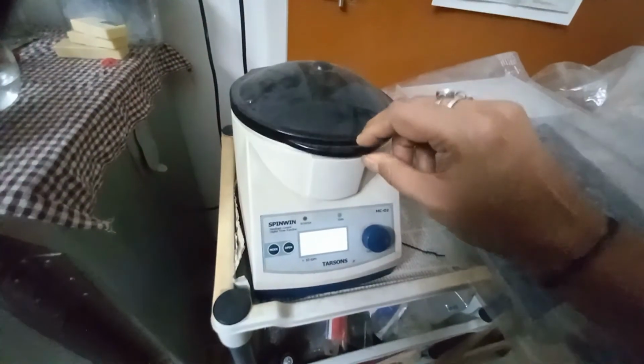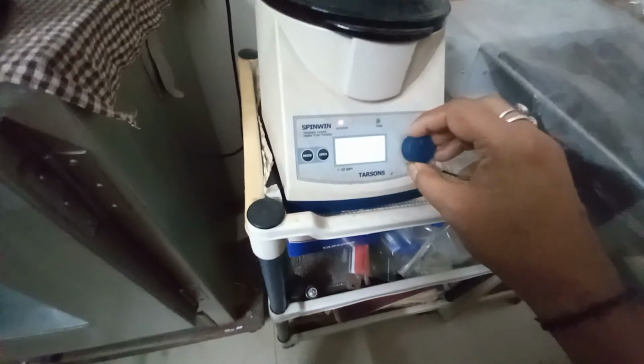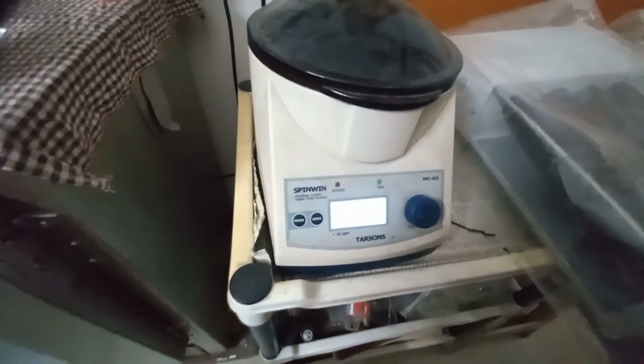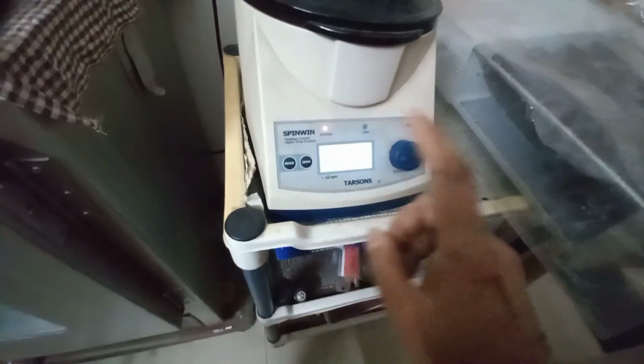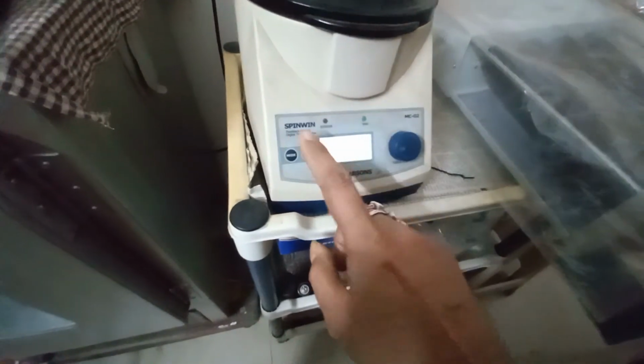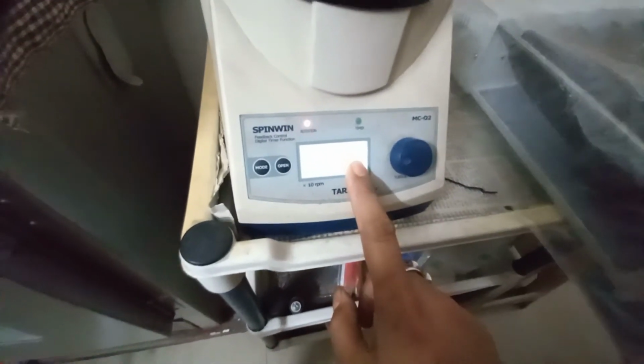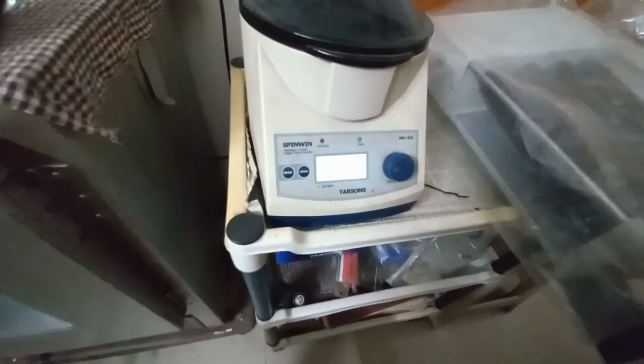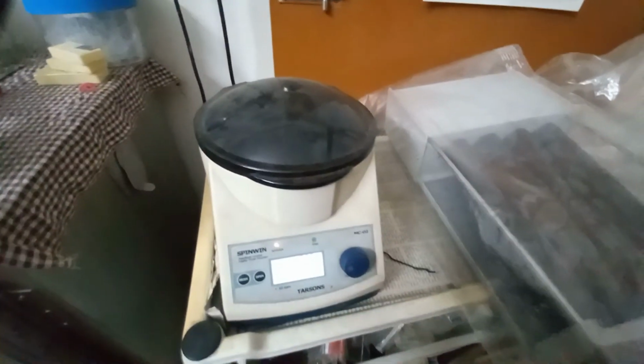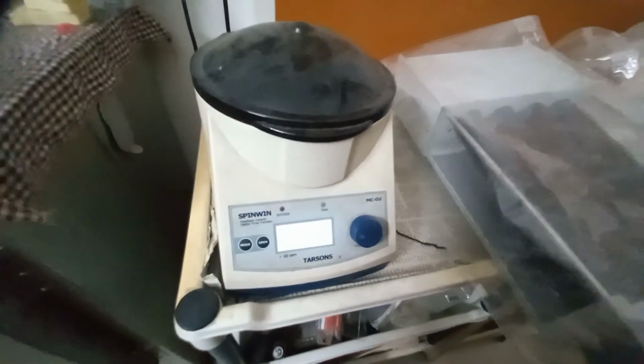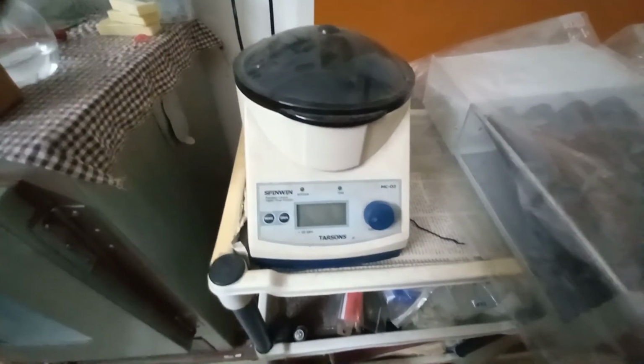Then you close the centrifuge and you start controlling. First you have to control the speed, then you have to change the mode and set the timer. Then again you bring it to the first display mode and push the switch and the centrifuge will start. So this is a very small video. As you can see, this is a Tarsons centrifuge. This is not very costly, but it is around 40,000 rupees.